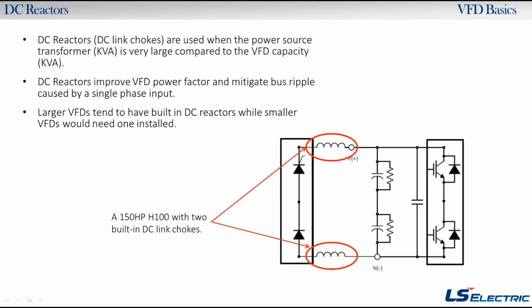And then larger VFDs also tend to have built-in DC reactors. So for us, 30 or 40 horsepower and above are mostly going to have built-in DC link chokes. On the H100 in this example, we're showing a DC link choke on the positive and the negative side of the bus. So you may see that sometimes, just to split it up on some of the bigger ones.